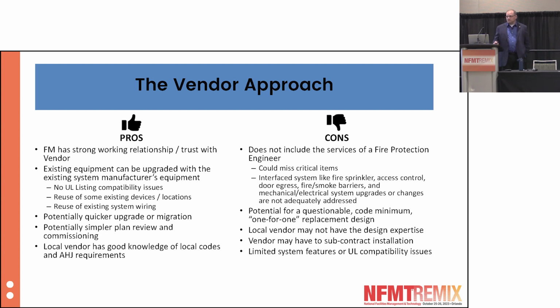We have ADA codes that our pull stations, as an example, need to be installed 42 to 48 inches above the floor to the operable part of the station. Well, they clearly didn't want to move this pull station. It was installed at 60 inches, which was perfectly legal 25 years ago. It's not legal today. Well, they didn't want to chip away at their precious green, lovely tile that they have there. So they simply screwed a piece of plastic to it. Said, see, the operable part is now 42 to 48 inches above the floor. I pity the AHJ who tried to accept that.